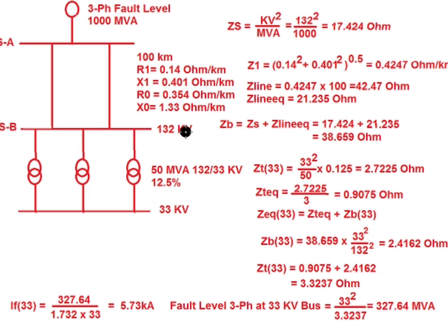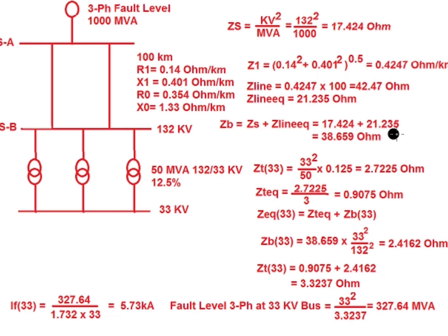At substation B, the total impedance combining the source impedance and equivalent line impedance is: ZB = Zs + Zline_equivalent = 17.424 + 21.235 = 38.659 ohm.